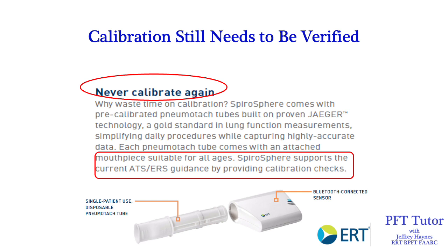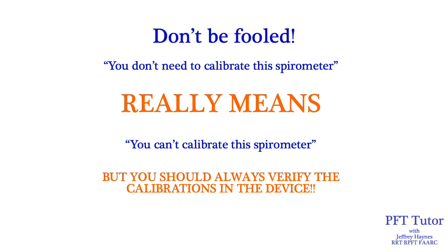Another calibration myth often associated with handheld or office spirometers is that you don't need to calibrate these — they come with pre-calibrated pneumotach tubes. That is true that you don't need to calibrate them because they're pre-calibrated, but that doesn't mean you don't have to verify that the calibration is accurate. Don't be fooled: when a manufacturer advertises that you don't need to calibrate their spirometer, what this really means is you can't calibrate it. However, you still need to verify that the calibrations are accurate.